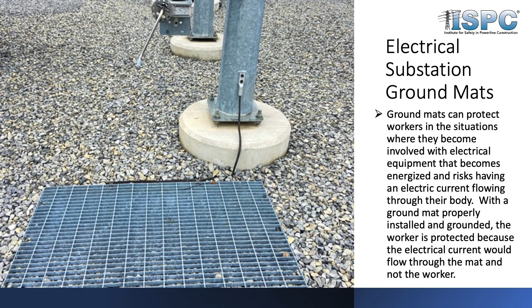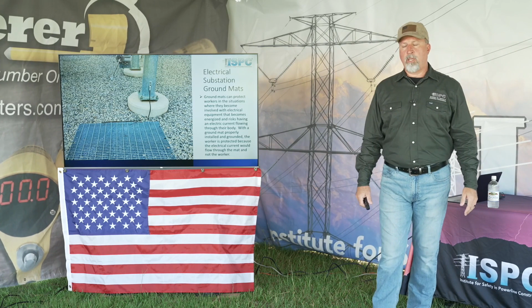What it does is put you at an equal plane with everything in that area. So if something does go wrong, your best course of action, unless there's debris falling from the air, is to stay on that substation mat — then you're at an equal potential. If you hop off that mat and run, you're going to be susceptible to step potential. Everybody's heard the adage about throwing a rock in the water and the ripples going out — it's the same thing with step potential. So if you leave this mat in an incident, you could be susceptible to step potential.